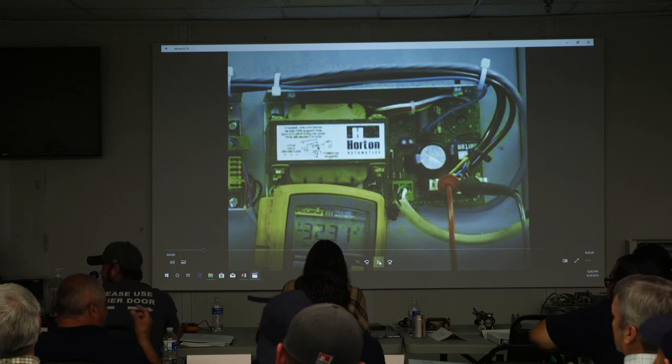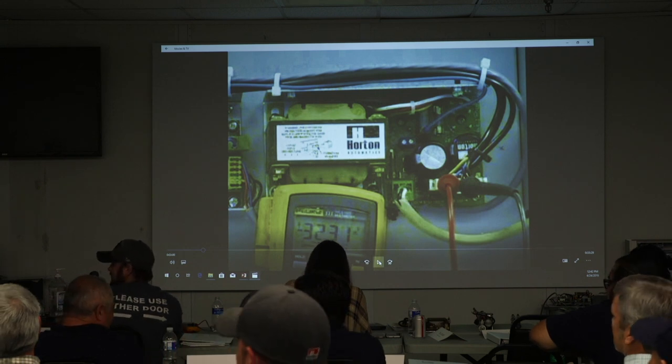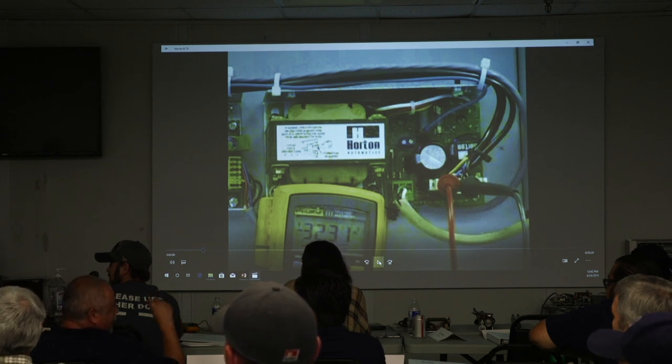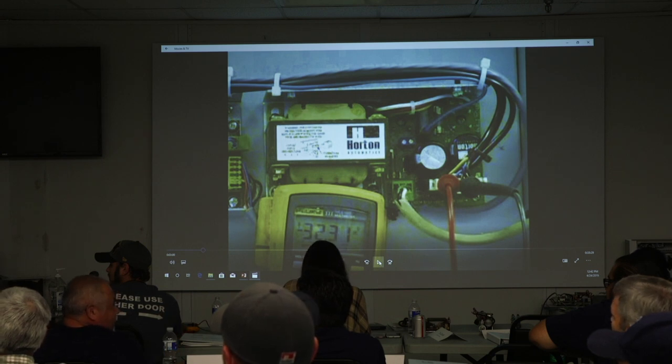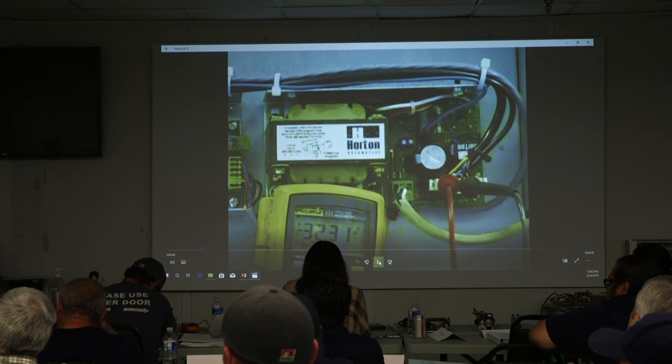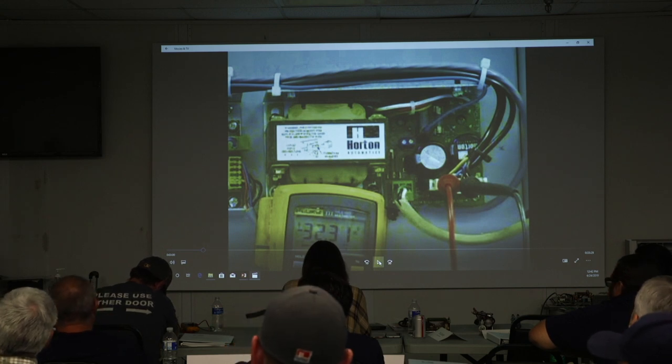There's something else that you can do that not a lot of people do. You can go to the AC volts with your meter and go to each end of the fuse. If you see voltage, the fuse is bad, because if the fuse is good, the electrons will take the path of least resistance through the fuse, and you'll see zero when you're on the AC scale looking across the fuse. Everybody catch that? Everybody understand that? Okay.